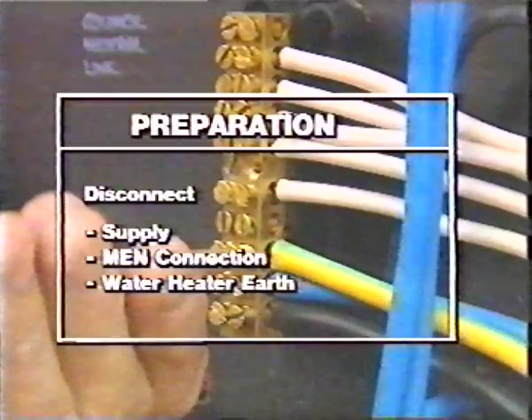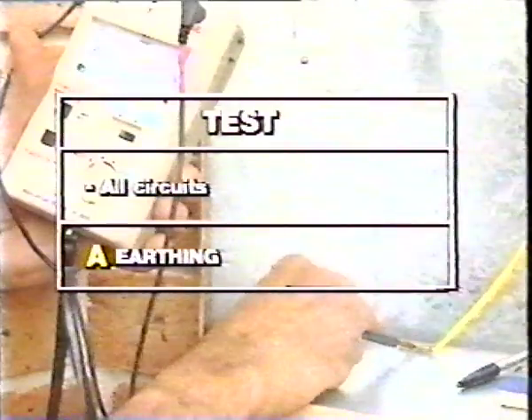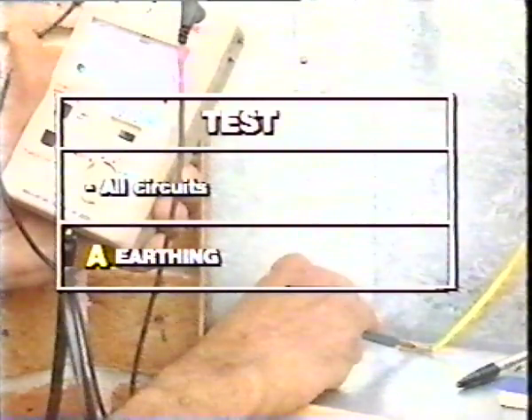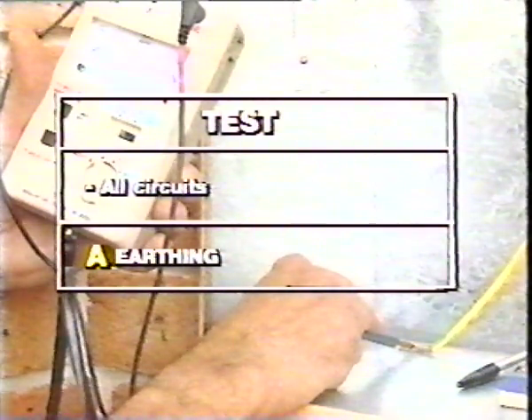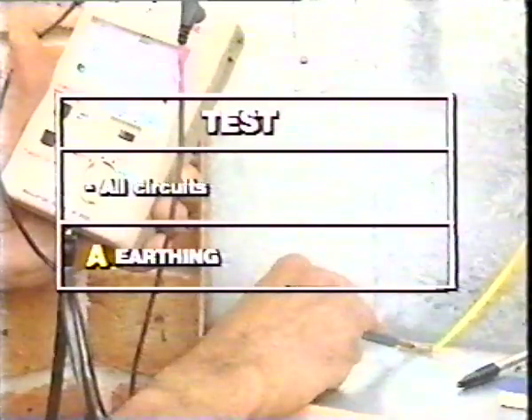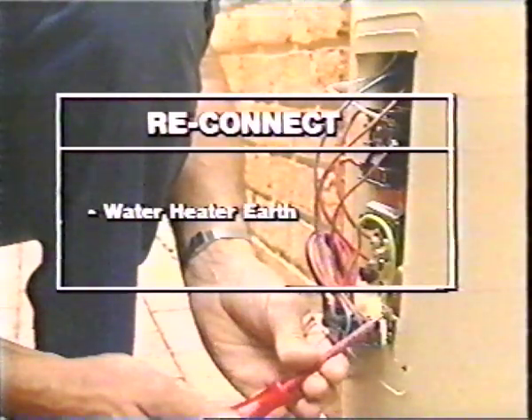Regardless of whether supply is available or not available, the preparation should be the same. First, disconnect the supply. Then disconnect the MEN connection and the water heater earth. Now test all circuits for earthing as in test A. When all points required to be earthed have been tested, reconnect the water heater earthing conductor.